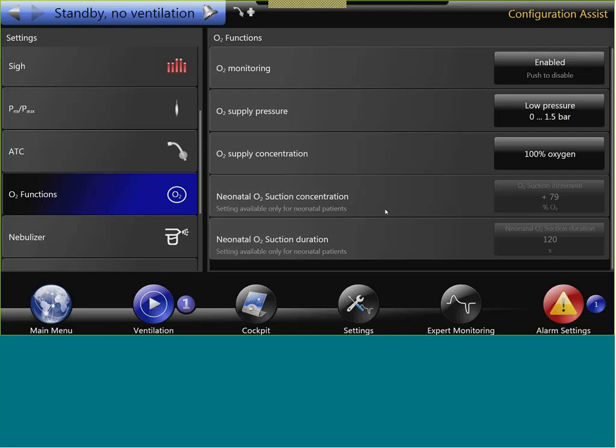Good. What is the maximum acceptable leak percentage during use of the AVM mode? This question is coming from Khalid. It's where you set it, but of course the bellavista, or the AVM, would maybe struggle if you set 100%. AVM would start to work and you won't get leakage alarms, but you will see that AVM is not working properly at the moment. So it's not about what percentage of leakage.